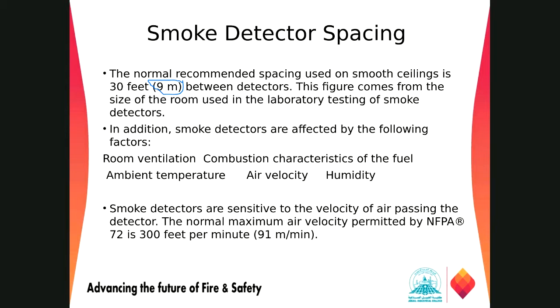At the time, smoke detectors are affected by the following factors: the room ventilation, combustible characteristic of the fuel, ambient temperatures, air velocity, humidity, right? So if you are installing your detector nearby diffusers from the HVAC unit, air conditioning unit, and the air is coming with a high velocity, it will not allow the smoke to come nearby the detector because of the high air velocity. It's just moving on to the other side.